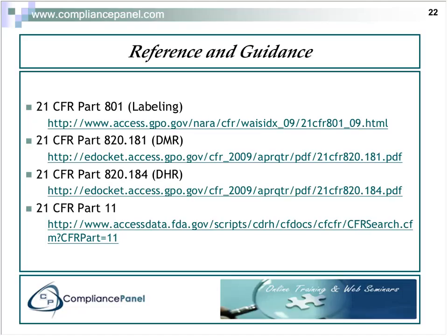A couple of other references are available in guidance documents. There's one for using third-party software included within a medical device, which is a very good guidance document. You can find that by just going to the FDA guidance site and entering third-party software.